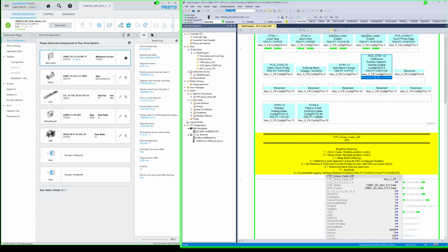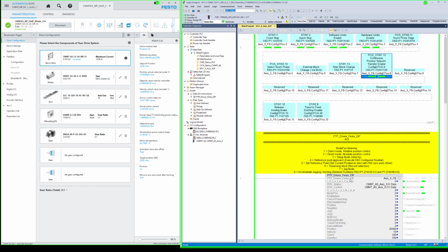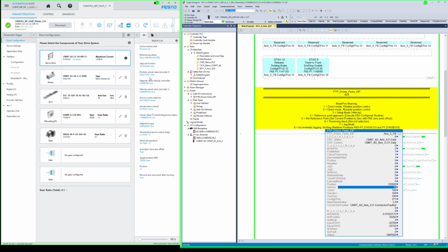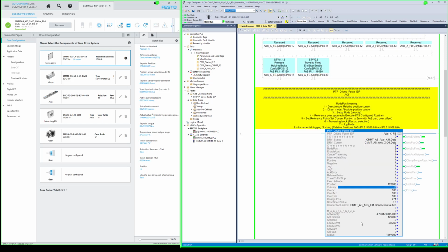The alternative is to use what's called continuous position set point transfer. So you enable this bit. Okay? So you can turn this rising edge off because we're not going to need this anymore. As soon as we enable this, the mode becomes active, and any change in this position target right here, if you look over here, enter, it's immediately got a new set point and it's moving to that based upon these parameters right here. Okay, so that is what the concept is for position transfer continuous. Again, if you put in a high move here and it's in the middle of the process here, and then you change it, it's immediately going to stop and start to execute the movement that you've requested. And that is the concept of continuous set point transfer.